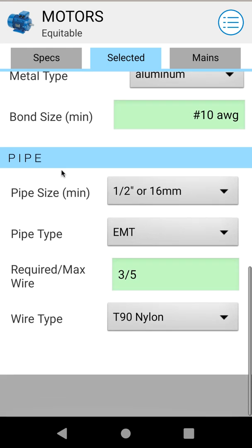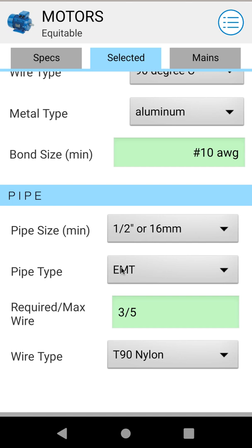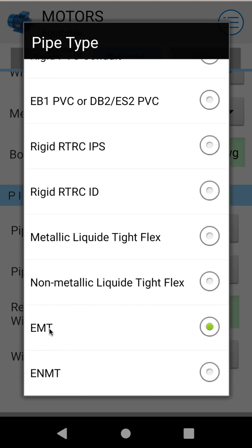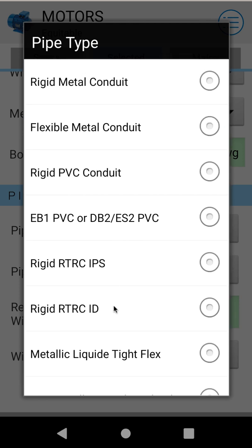After that you'll see bond size — this is your bond wire that you'll want to run in your conduit if you choose. Then after your wire section we get into your pipe recommendations. Since we're running aluminum number 10, three conductors, we're going to fit that into a half inch conduit. You can choose your pipe type — any conduit types included in your code book, such as EMT, rigid, or PVC. This result shows how many wires are required in your pipe — three, which we specified as number of conductors — and how many will actually fit in a half inch pipe, which is five. This gives you a good indication of how full your pipe is.